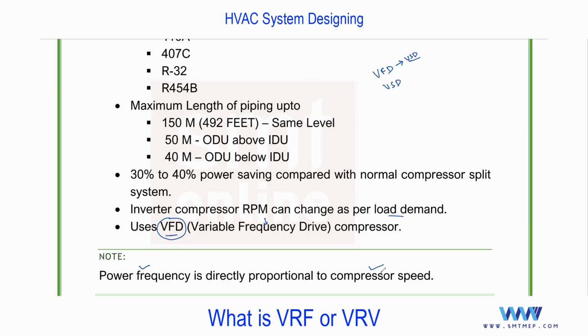As the frequency increases, the RPM of that compressor also increases. As the frequency decreases, it will also decrease. This is VFD. I'll give you more points related to it. But first, if the system is only VSD, it means it can change the speed without changing the power consumption, by using gears or pulleys, but the motor speed stays the same. We are changing the fan motor speed RPM by changing the size of the pulley, or by using gears. In that case, the system is only VSD. There is no change in the power consumption.